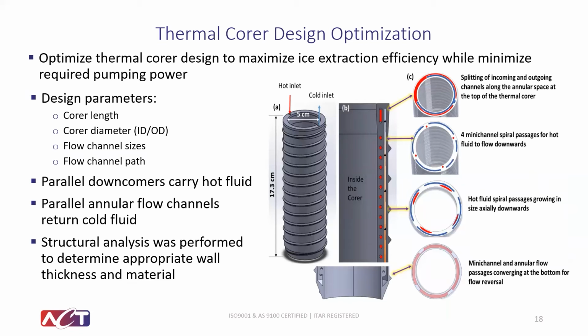One of the objectives in Phase 2 is to optimize the thermal corer design so that we can have a maximized ice extraction rate and reduce the pumping power for the heat transfer fluid to go through the mini channels. The design parameters include thermal corer geometry, length, and diameter. Also, the mini channels distribution as well as the size.